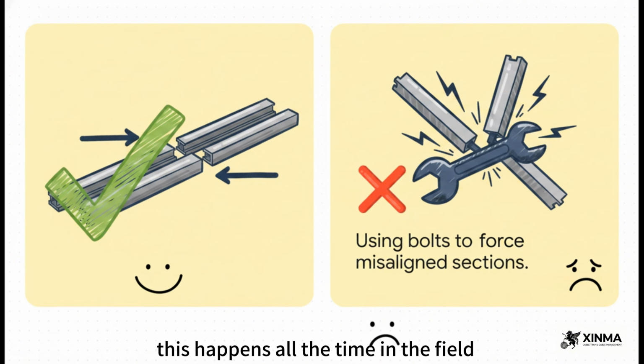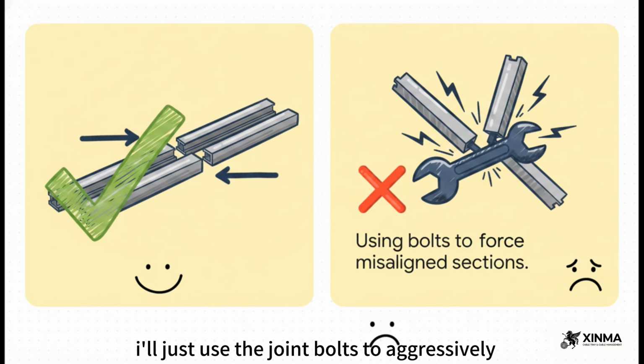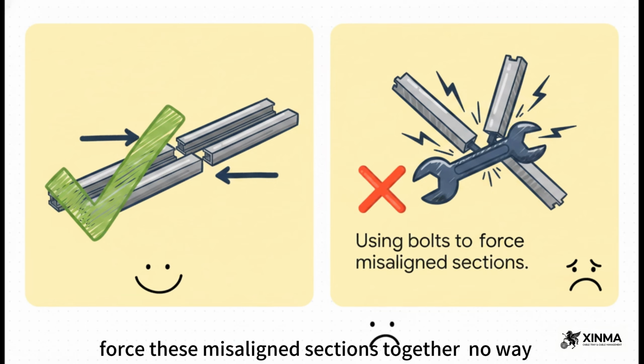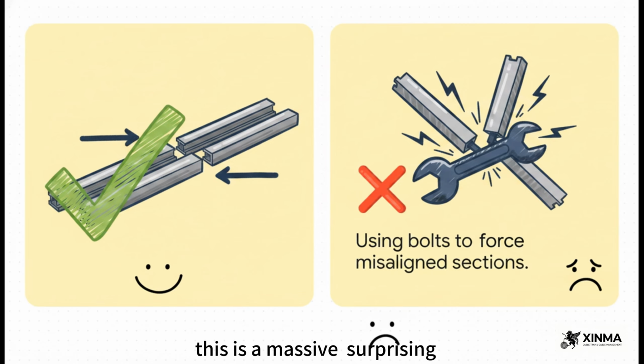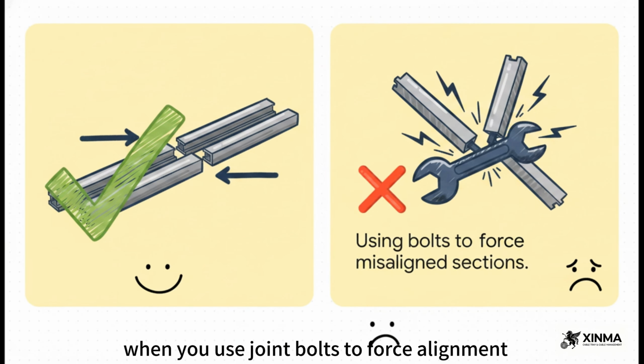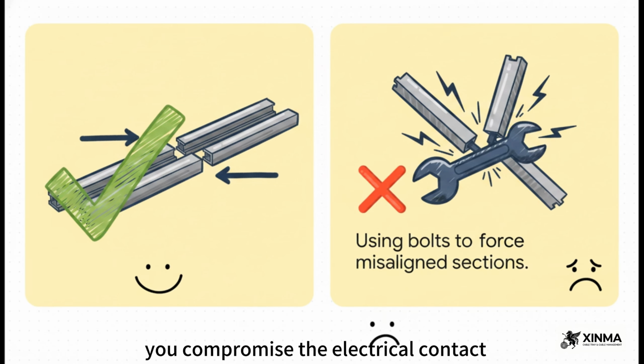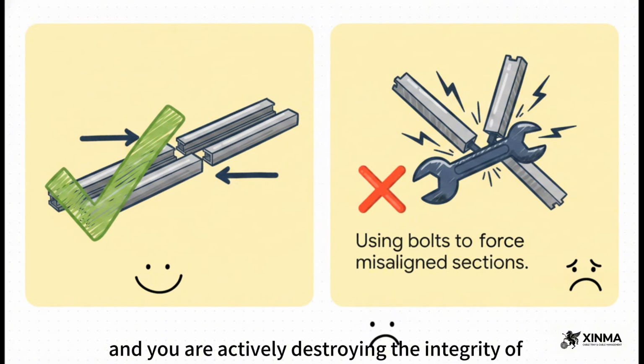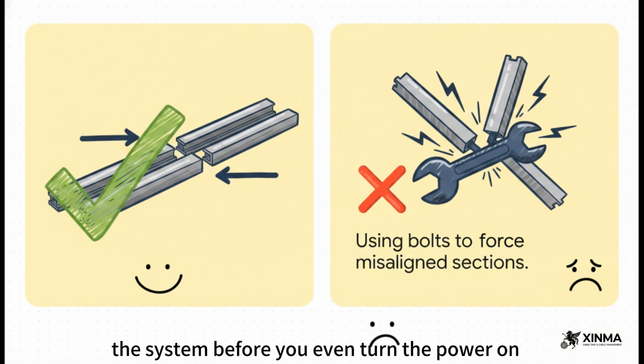This happens all the time in the field. Sections are slightly off and an installer decides to just use the joint bolts to aggressively force these misaligned sections together. This is a massive, surprising, and all too common field error. When you use joint bolts to force alignment, you introduce extreme mechanical stress, you compromise the electrical contact, and you are actively destroying the integrity of the system before you even turn the power on.